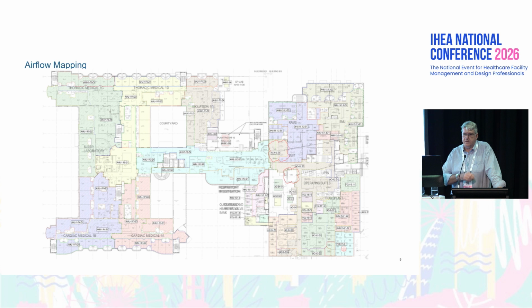More recently, chasing Lomentospora through one of our hospitals after a couple of clinical incidents, we were really struggling to understand that complex mix of fixed ductwork, flexibles, where the AHUs were located, and which zones they were coming off. So we sat down with all the mechanical drawings and went through them in detail, and mapped out through all our floors which AHUs and zones were feeding which areas. It was actually quite surprising—we found a couple of fan coil units we didn't know about, which were potentially contributing to some of the clinical issues we were having. Another very useful tool.